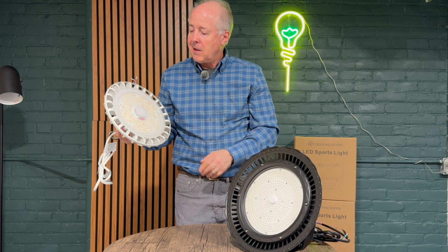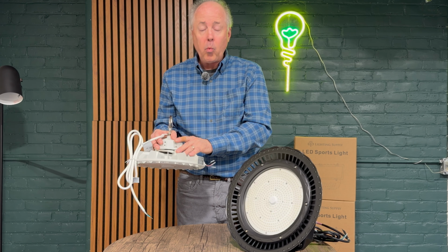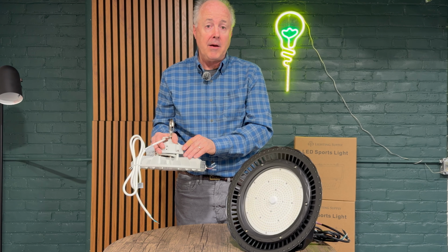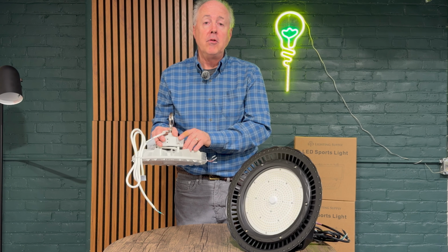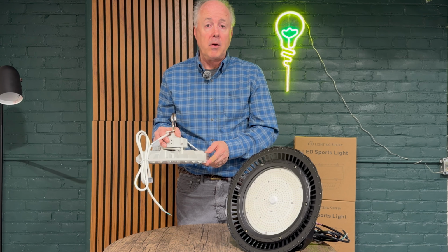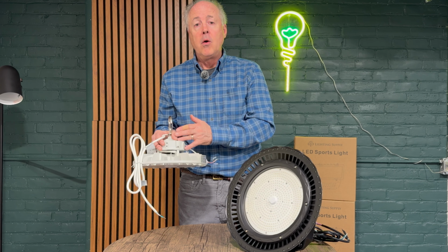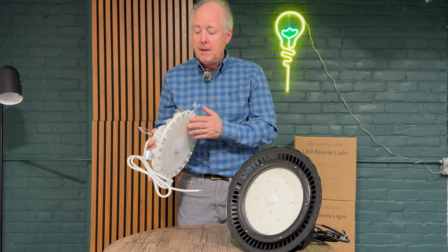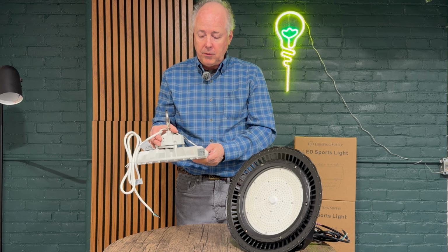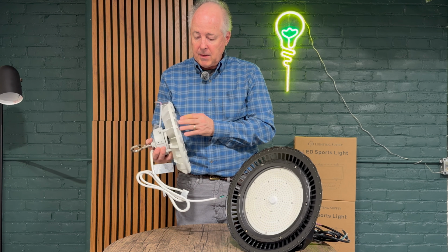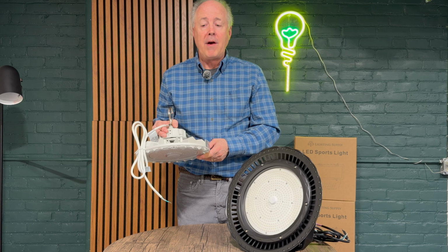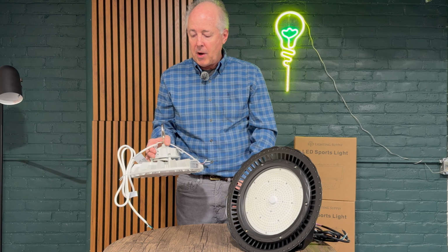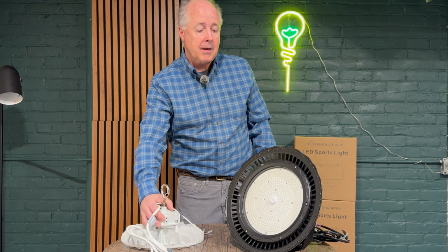But it's great. It'll light up your warehouse, your shop. They are wattage changeable in almost all cases now. In this case, this is a 200 watt that puts out 33,000 lumens, more than you need to replace a 400 watt metal halide, and you can go all the way down to 120 watt. It can be switched in the field. It also supports 4000K or 5000K. We traditionally recommend the 5000K, and it does have the dimming wires. You can get a pendant bracket.